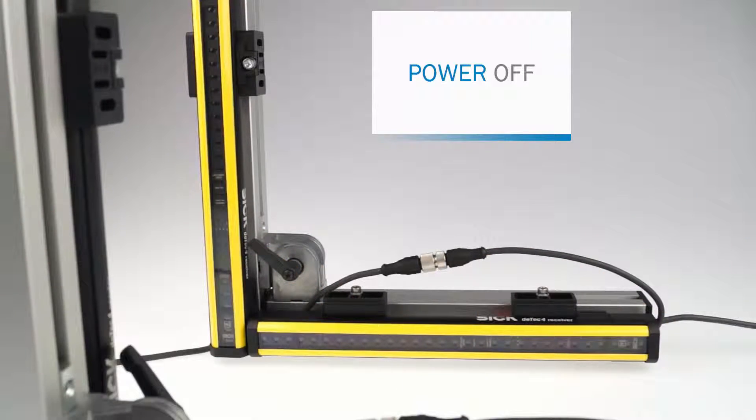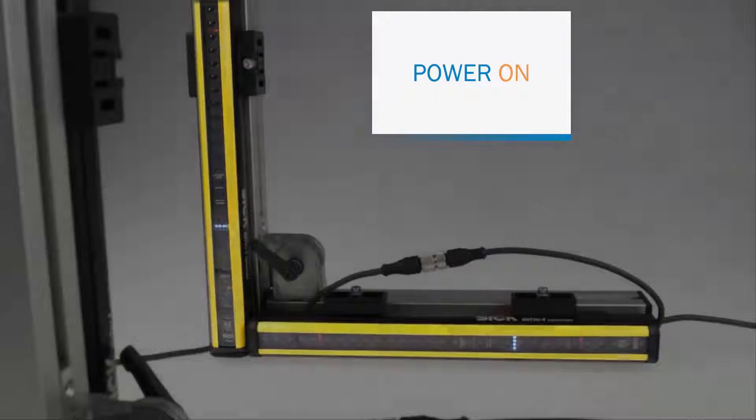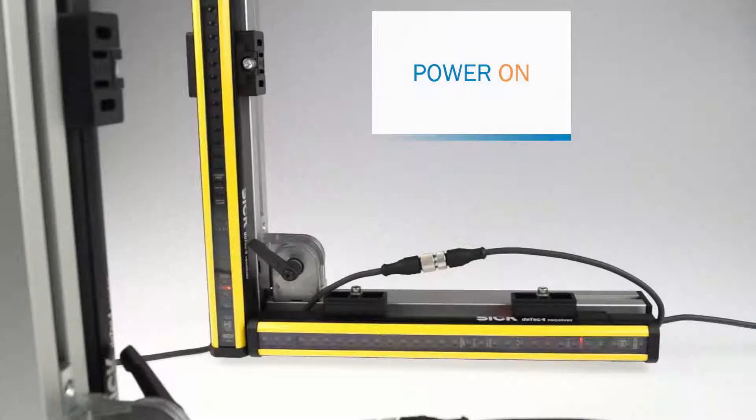If everything is wired correctly you can connect the system with the power supply again. The devices which are connected directly to the power supply represent the host devices while all other devices are guest devices. Now the field LEDs of the devices are flashing green. This is the sign that the devices have entered the configuration mode and the cascading has been successful.